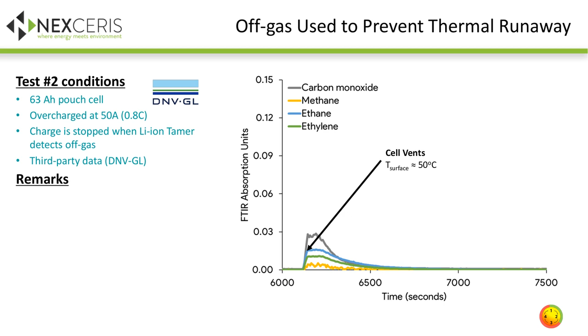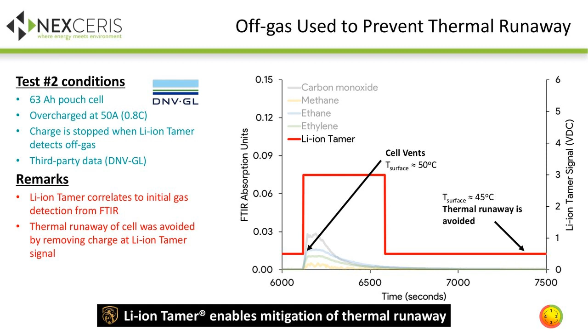And what was able to be demonstrated here, if you look at the cell vent, the surface temperature when the cell vented was about 50 degrees Celsius. And then sometime down the road, that cell continued to cool off, and that surface temperature never indicated that the cell went into thermal runaway. Kind of the purpose here is to demonstrate some of the new techniques that are coming down the road for fault detection within battery systems that can supplement and really provide some earlier warning prior to the reliance upon smoke and fire detection alone, which is in the containment region that we looked at on the battery failure chart.